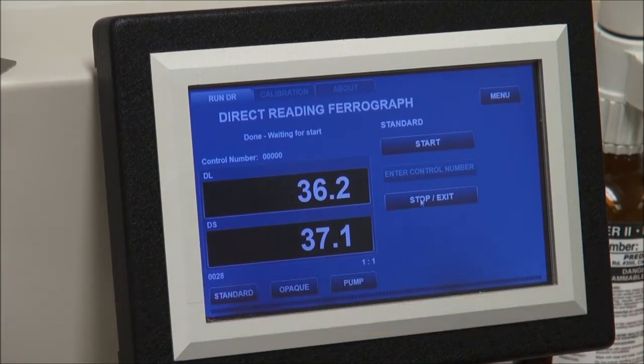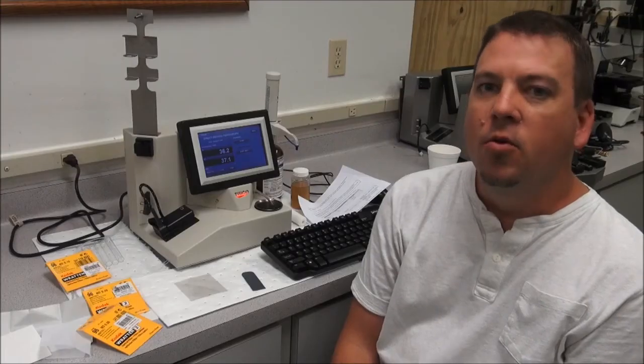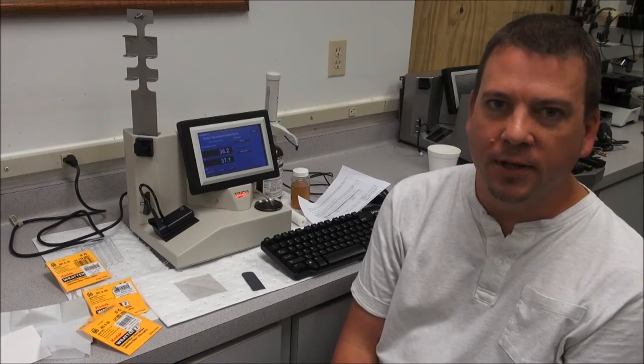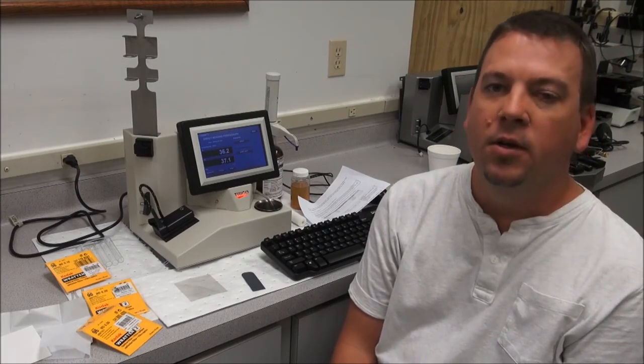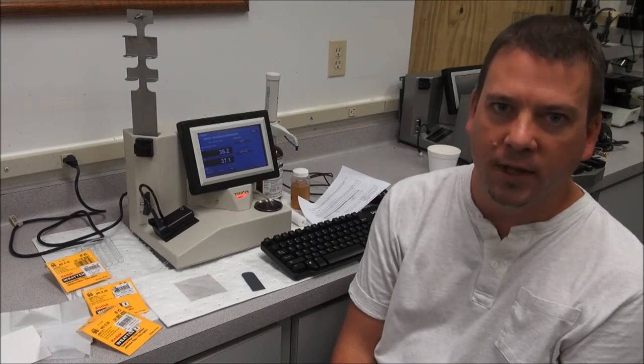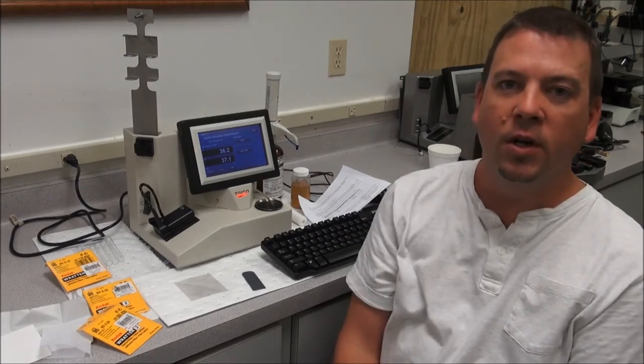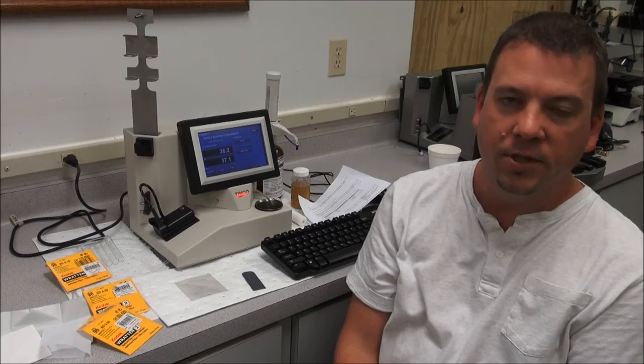Remember that when inserting and removing density films, failure to remove films during sensor zeroing will cause L and S readings to be 30 points lower than expected. Once the 0.1, 0.2, and 0.3 density filters fall within the range located in your manual, your unit is calibrated and ready for oil testing. If you have any questions during your DR calibration, please contact Trico Corporation for additional assistance.